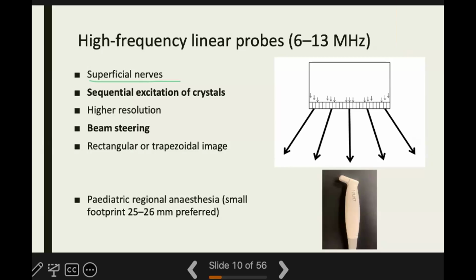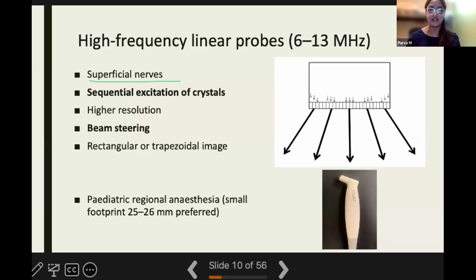Now, this beam steering basically means that your sound beam is not just directed in one direction. When you keep your transducer in one direction, the beams that are produced from the transducer can be in multiple directions so as to gain the image from all angles, thereby giving you a very beautiful image with lesser speckle, and allowing almost all minute details to be caught by this principle of beam steering. Normally, it's commonly known that the linear frequency probe is only going to give you a rectangular image. But a lot of our newer machines have a function where we can even gain a trapezoidal image, that is basically gaining a wider field of view.